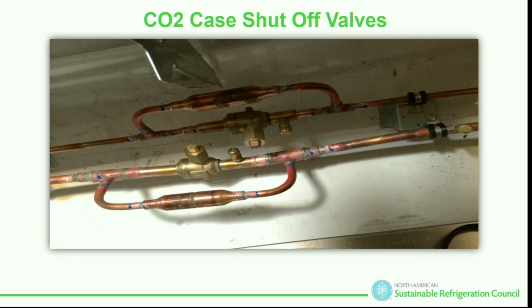All right, CO2 case shut-off valves. Once again, make sure that you are checking these to make sure that they are in the proper direction. Your check valve should always be faced in the direction of the rack, so that if the pressure in the coil goes up higher than the pressure on the other side, it wants to vent in that other direction. Sometimes you will see Sporlan valves that are internally checked, so make sure that you check those out in RTFM. Read that manual and make sure that you look to see how those operate as well.